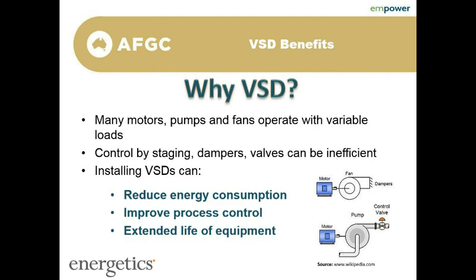So instead of using those control measures, using a VSD has a number of benefits for your site. The largest one is the reduced energy consumption. This is usually what gets the installation of these across the line. Economically, it makes them stack up. But there's also a couple of other benefits. It often improves your process control, as there's variable loads and changing conditions on your site. VSDs give you a wider range of control rather than some of these other techniques. And there's also potential for extending the life of the motors and other equipment.